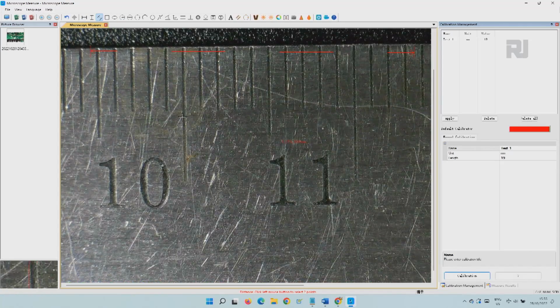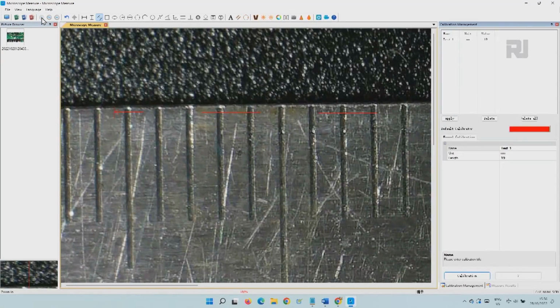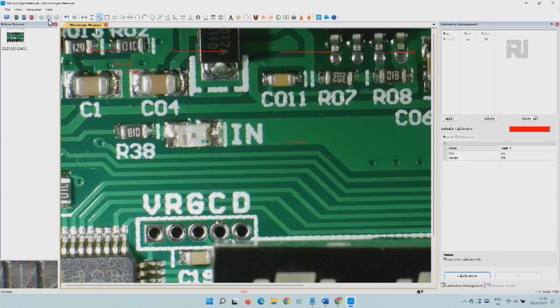Now let's measure from here to here. Let's zoom in first so we can get an accurate reading. Let's go 1 millimeter and see if it gives us 1 millimeter. It shows 0.99. That's very accurate, so the calibration is done. Now if I want to measure this length from the middle up to the middle of this corner and click somewhere you can read, it says 11.24 millimeters.